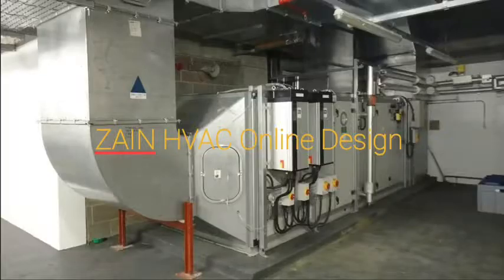The second AHU which you're going to look at, this is slightly different. It's only got a cooling coil on it, so the air's coming in here and it's being sent off again, off into the space. But you'll notice that this one has got some VFDs on it, some VSDs, variable speed drives or variable frequency drive, and they control the speed of the induction motor, which is connected to the fan.